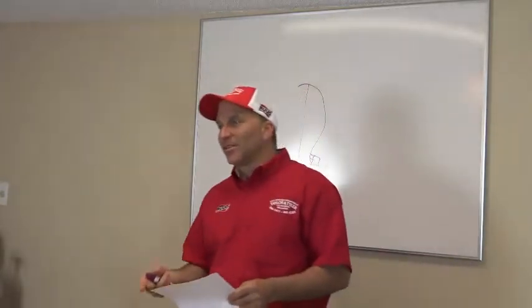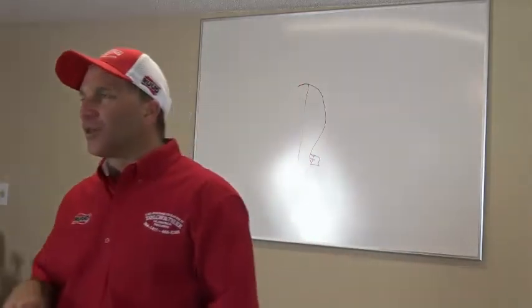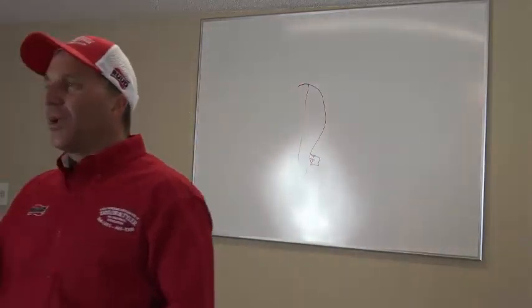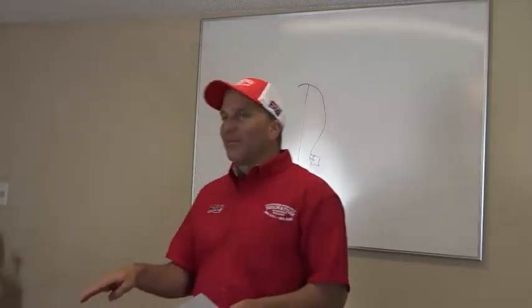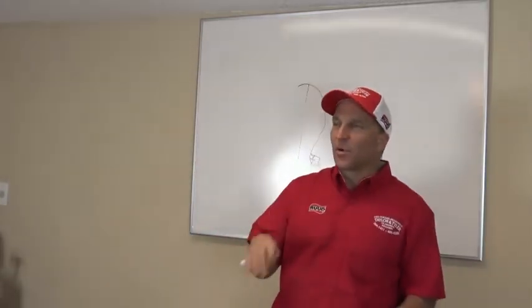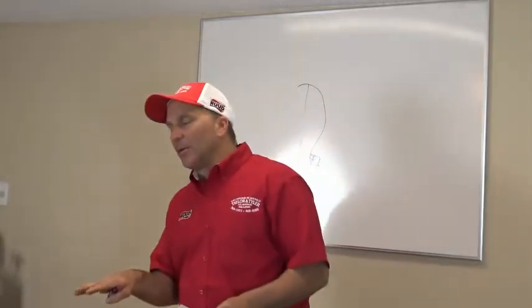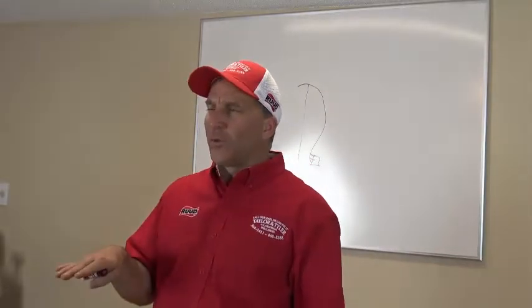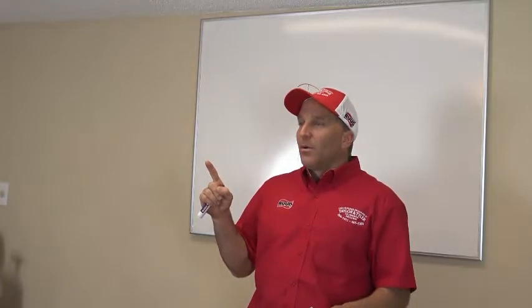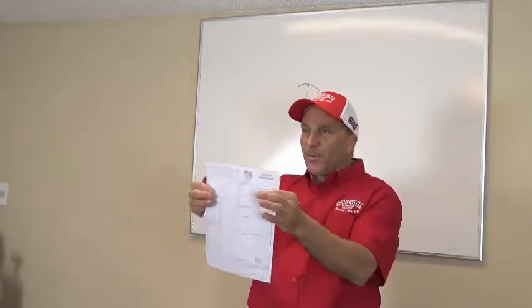And your subcooling is going to be high, and your suction pressure is going to be low, and your superheat is going to be normal. You're going to have a low head pressure, high subcooling, low suction pressure, normal superheat, high delta T. Well, you mean I got to go check all that stuff? Yeah, it's part of your paper. This is what you're supposed to be doing.